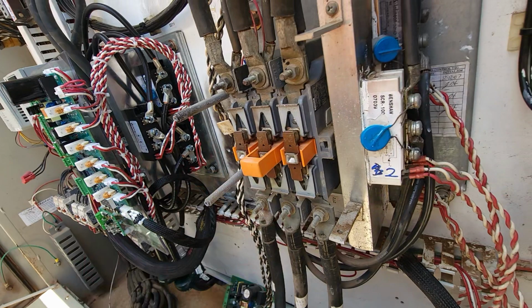Let's keep this in the chiller world. So starting off, the simpler one would be a soft starter. In a soft starter, we'll have a regular starter contactor, but we'll have a set of SCRs attached to the side of it. And what a silicon controlled rectifier does - with a VFD we use it slightly differently, but I'll get into that in a second.